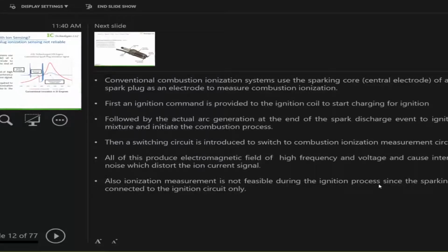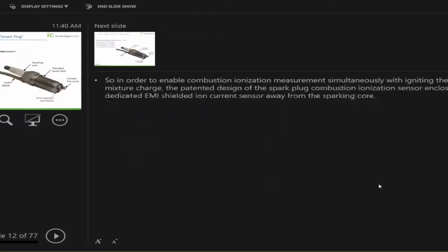All of this would produce a lot of electromagnetic field of high frequency and voltage and cause EMI interferences, which distort the ion current signal. So previous techniques were not able to achieve clear noise-free signals as we do. Also, ionization measurement was not feasible during the ignition process since the sparking electrode is connected to the ignition circuit only. But our designs, our patented designs.